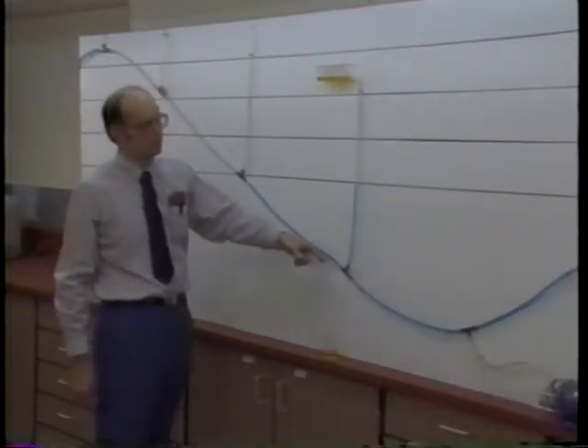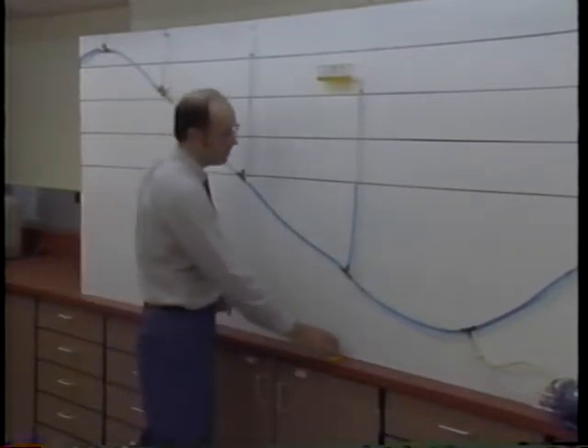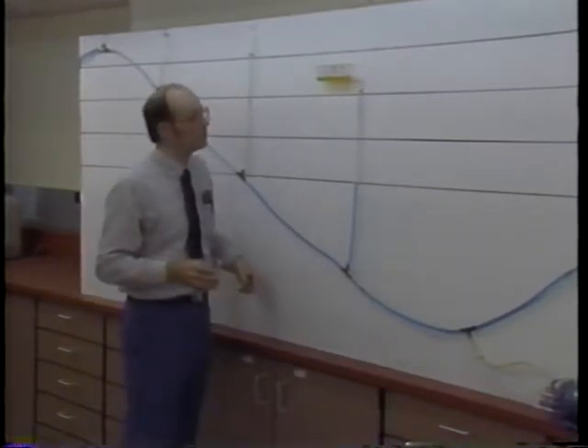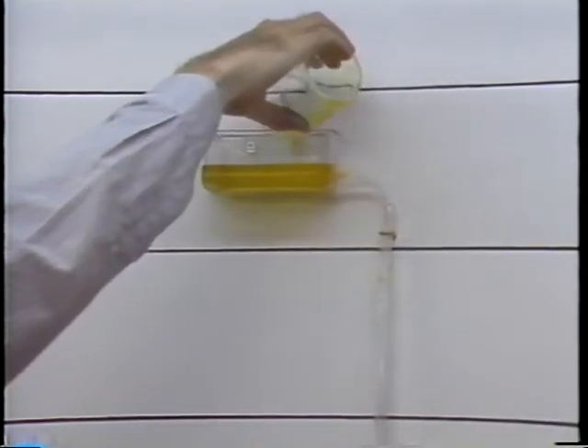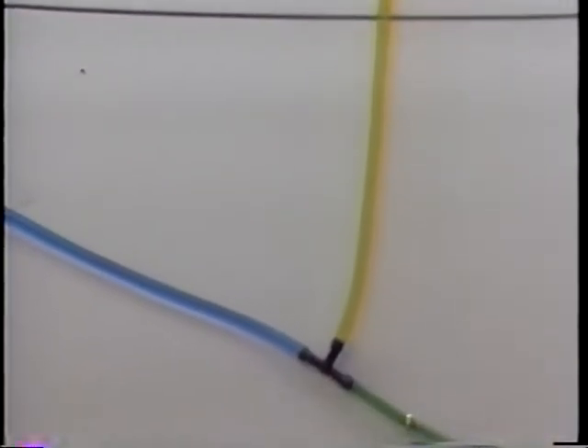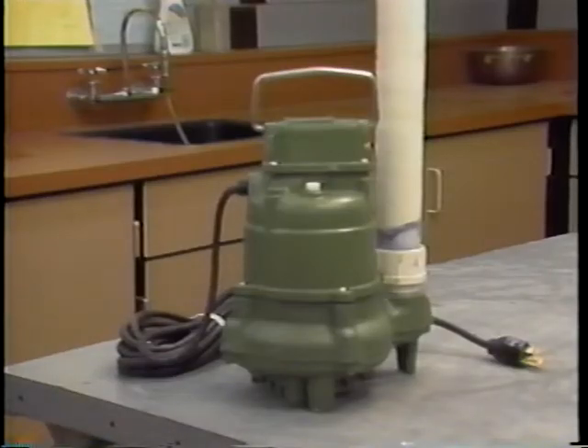The blue water represents effluent continuously flowing through the sewer. This yellow water represents effluent from a single septic tank. The effluent doesn't back up into the septic tank, and it passes through the low point and beyond. If a septic tank is below the sewer, its effluent can be discharged into the sewer by a small pump. An effluent pump like this one costs only about 60 cents a month to operate.